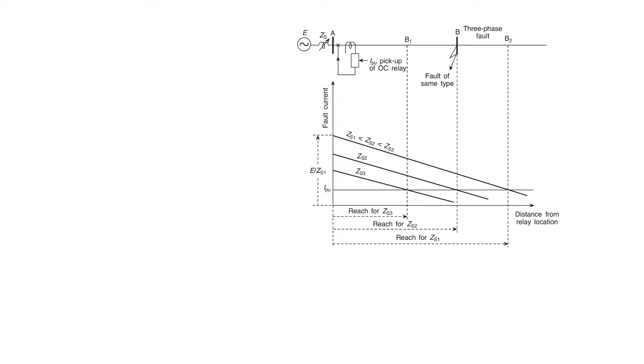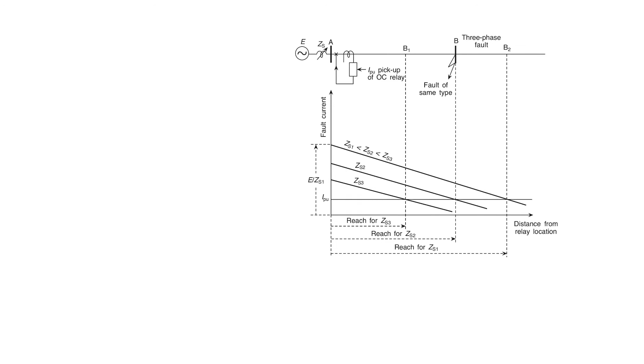Then it underreaches the point B1 with the source impedance ZS1, and overreaches to point B2 if the source impedance is ZS1. Again, this is not a desirable trait, as it will underreach and overreach depending upon the type of fault and the source impedance. Thus we see that the fault current is a function of the type of fault and the source impedance.